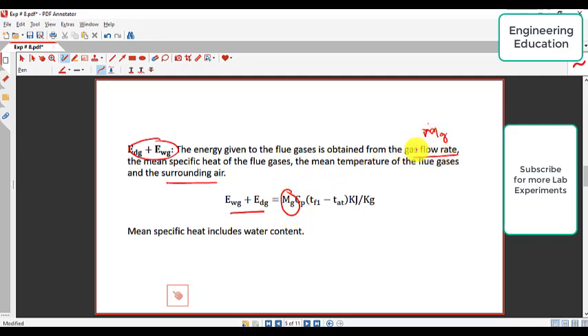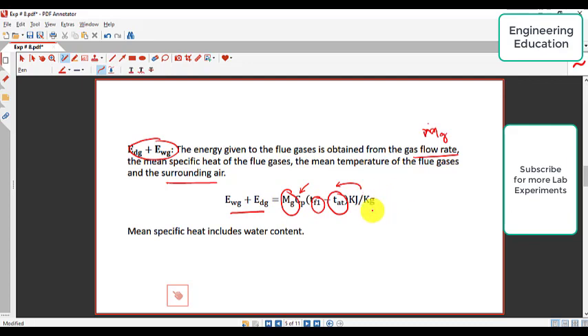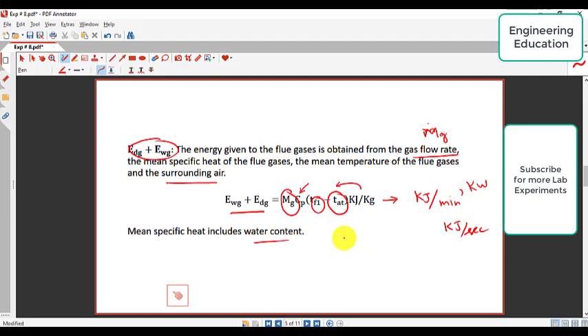The gas flow rate M-dot-G, specific heat capacity CP, flue gas temperature TF1, and atmospheric temperature TAT are used in the formula. The energy is measured in kilojoule per kilogram; multiplying by mass flow rate gives kilojoule per minute or kilojoule per second or kilowatt. Our calculations are mostly in kilojoule per minute, so we will represent all energies in kilojoule per minute.